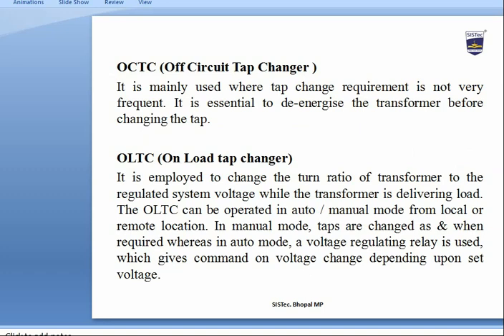OCTC is used where tap changes are not very frequent; the transformer must be de-energized before changing the tap. OLTC (On Load Tap Changer) changes the turn ratio of the transformer to regulate system voltage while the transformer is delivering load. The OLTC can be operated in auto or manual mode from a local or remote location. In manual mode, taps are changed as required; in auto mode, a voltage regulating relay gives commands based on set voltage.